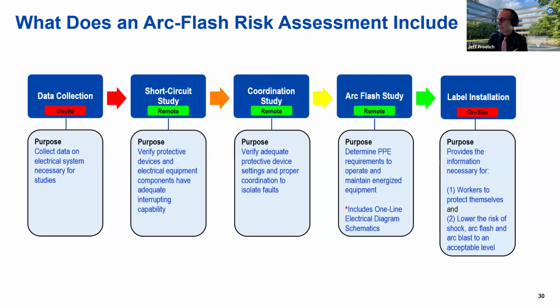You get into the coordination study, which verifies the adequacy of the protective device settings and proper coordination to isolate the faults. So it's going to look at the overcurrent protective devices and make sure they will operate in the specified time limits in order to clear the fault. They're going to look at relay coordination, design assessments, checking of the settings on these particular overcurrent protective devices, looking at fault clearing times. There are things such as time current characteristic review and those types of plots. They'll look at transformer protection, fuses or breakers to protect the transformers and cables from faults.